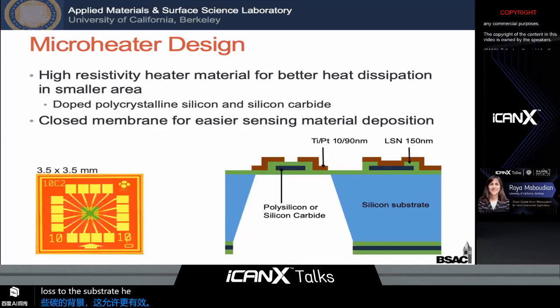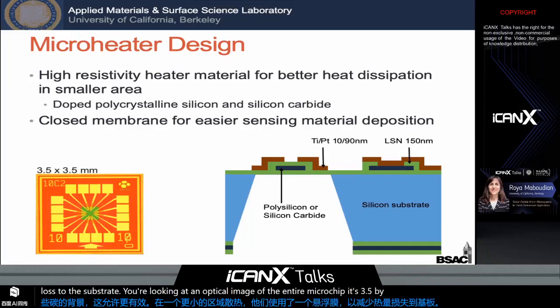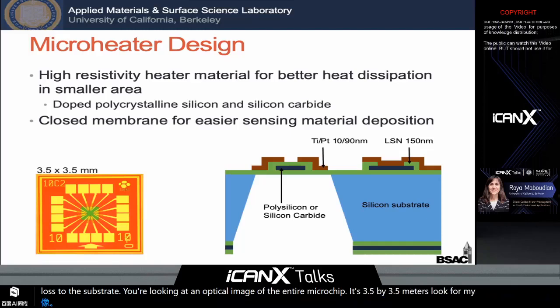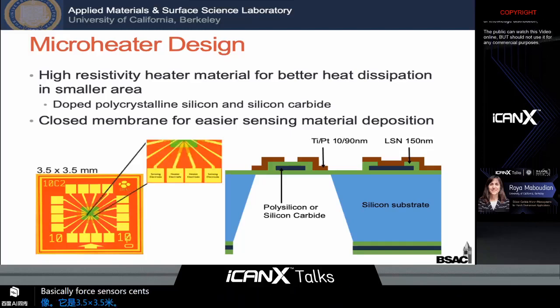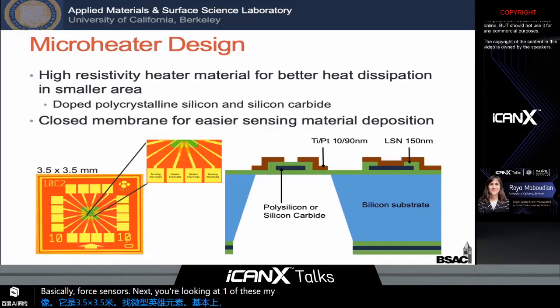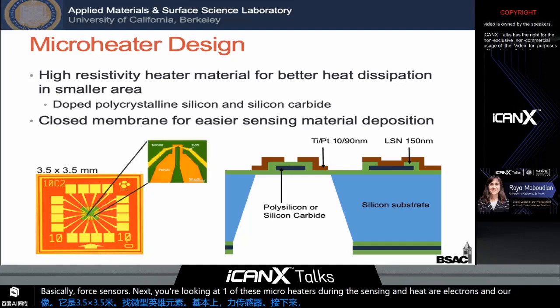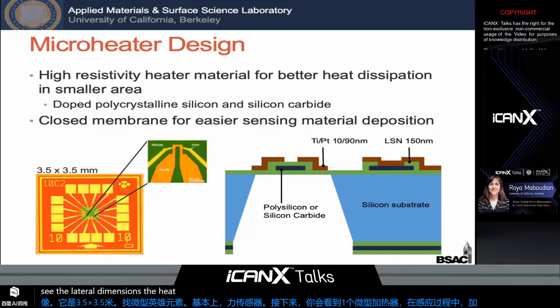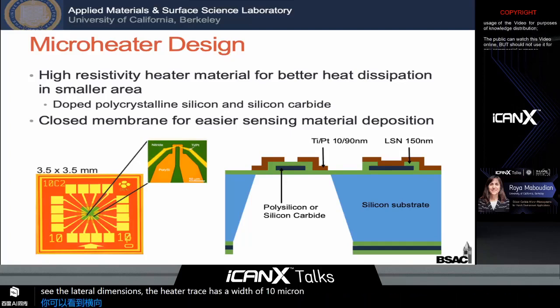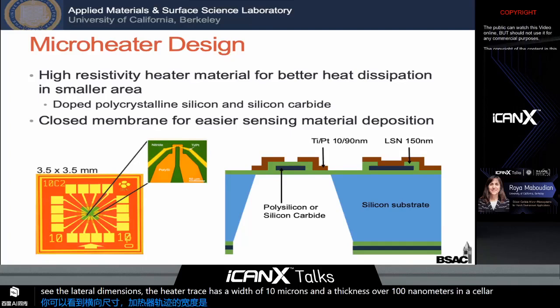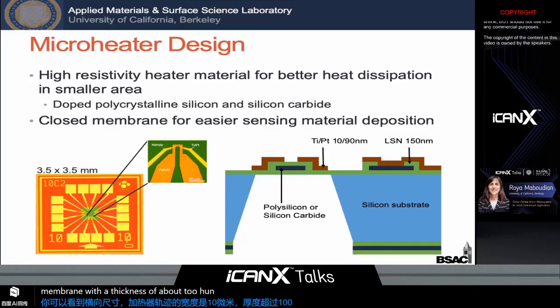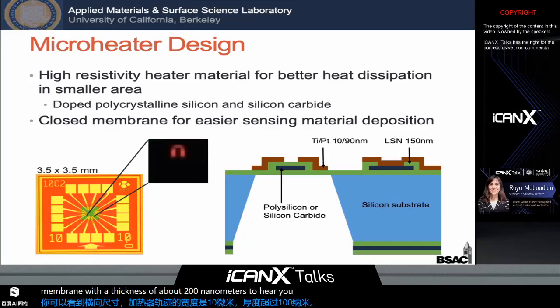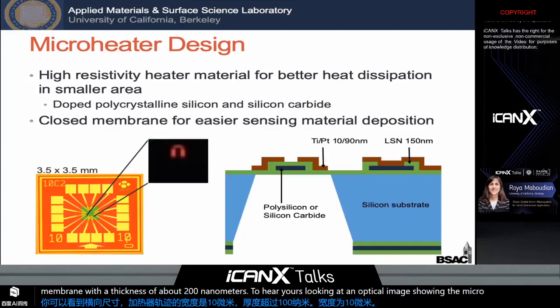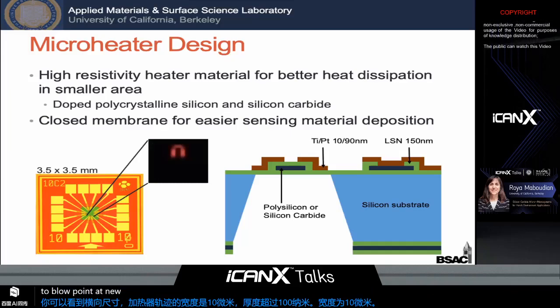Here, you're looking at an optical image of the entire microheater chip. It's 3.5 by 3.5 millimeter with 4 microheater elements, basically 4 sensors. Next, you're looking at one of these microheaters showing the sensing and heater electrodes. And here you can see the lateral dimensions. The heater trace has a width of about 10 micron and a thickness of about 100 nanometer in a silicon nitride membrane with a thickness of about 200 nanometer. And here you're looking at an optical image showing the microheater heated to glow point that we use for temperature calibration purposes.